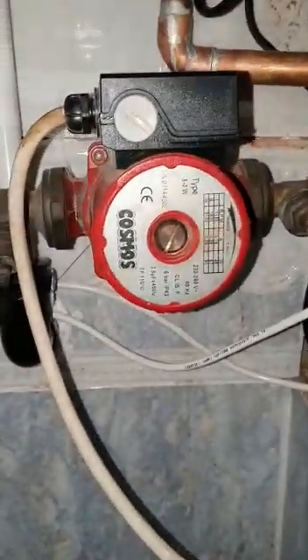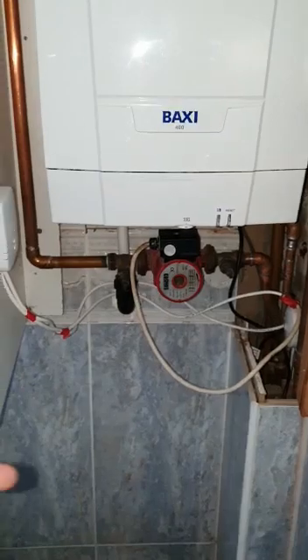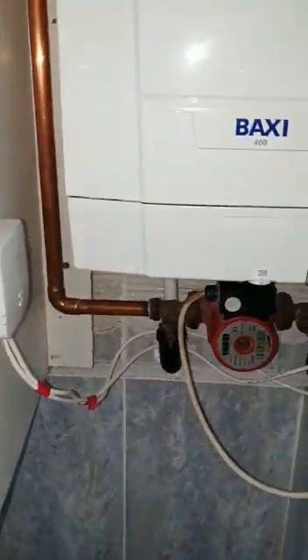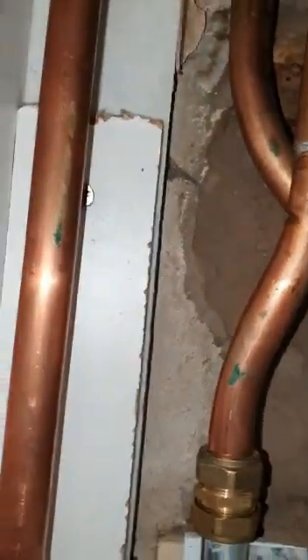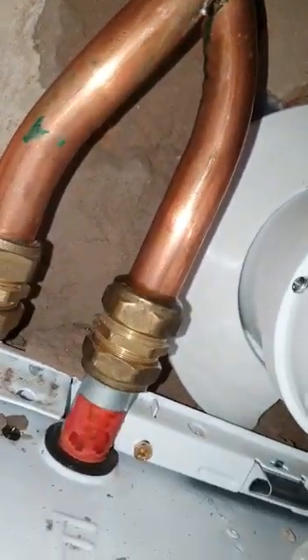This is the pump, and if you look underneath the pump, the pump has a direction of flow which you can clearly see goes to the right. If I stand back, you can see that the pump is pumping that way. However, if we trace this pipe up the side of the boiler, there it is — into that T, into the flow.